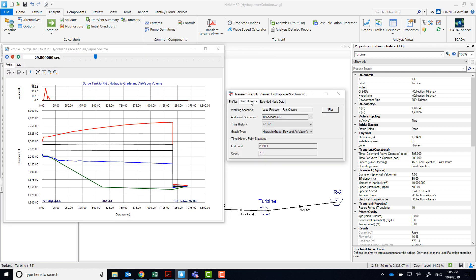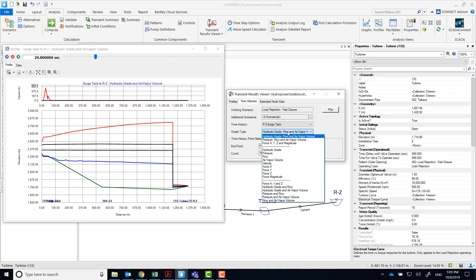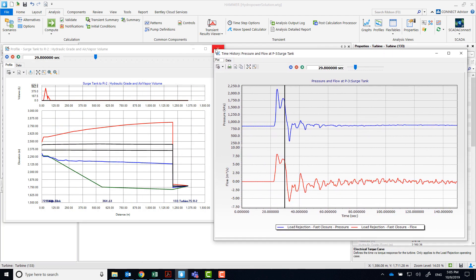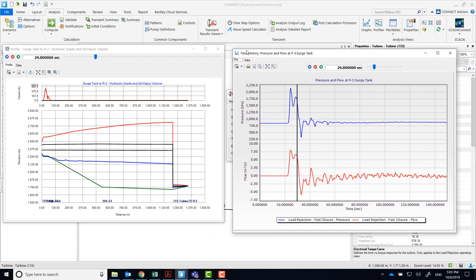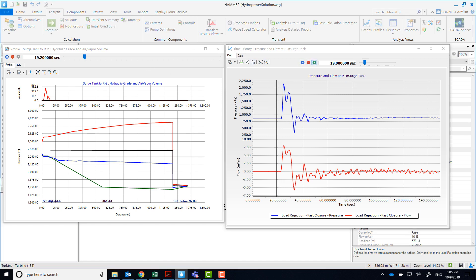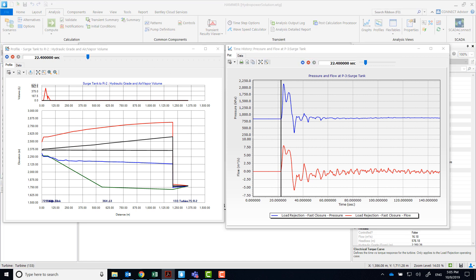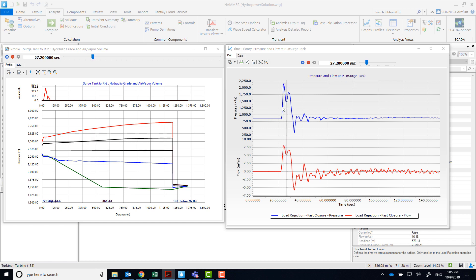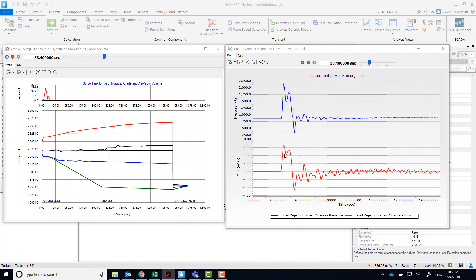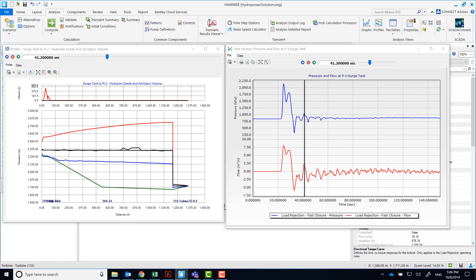Plot the surge tank to R2 profile for hydraulic grade and air or vapor volume. Open the time history for pressure and flow at pipe P3 at surge tank end. Notice that at about 22 seconds, the pressure upstream of the turbine spikes as a result of the wicket gate sudden closure. As the pressure increases, the surge tank starts to fill. At about 29 seconds, the surge tank starts to drain as the pressure drops. However, flow is restricted and it cannot get to J1 and J2 soon enough to prevent vapor pocket formation.